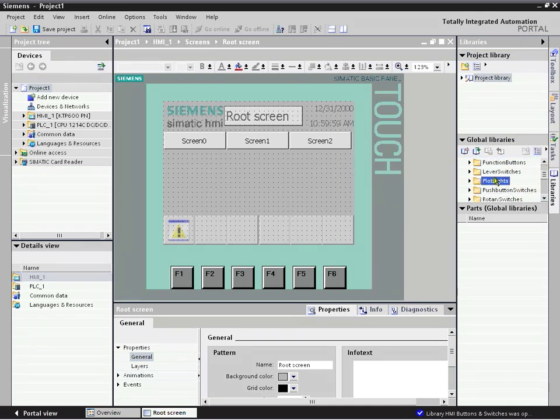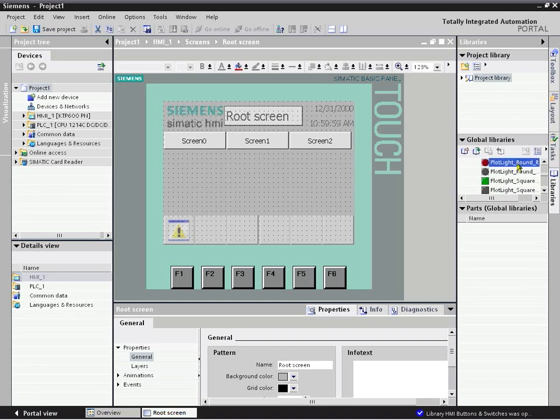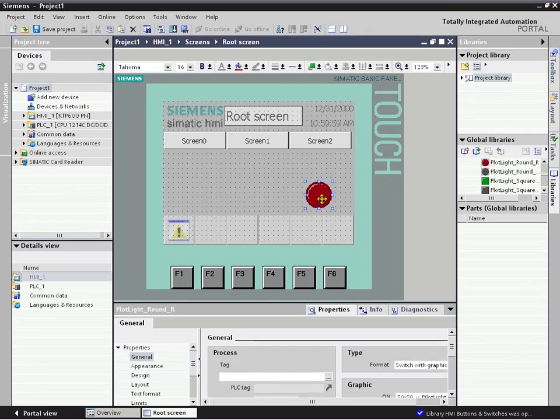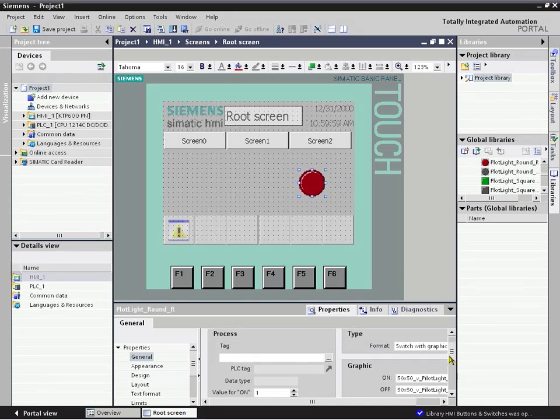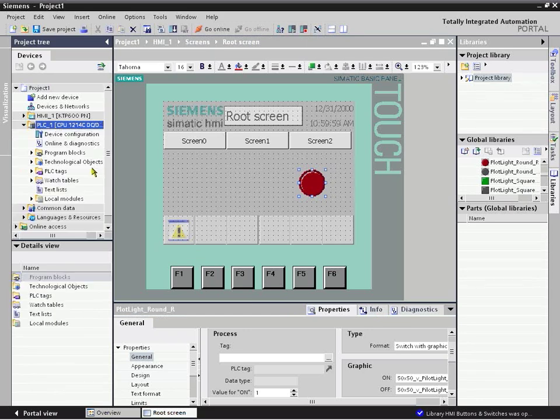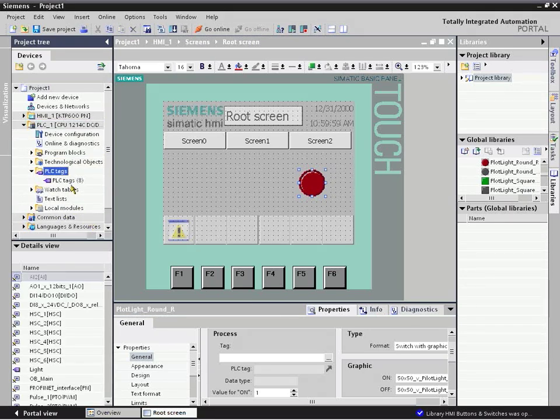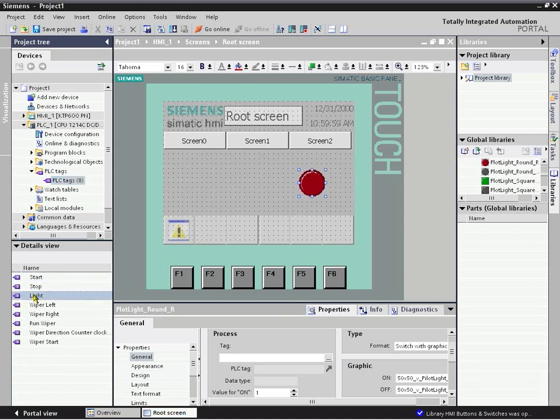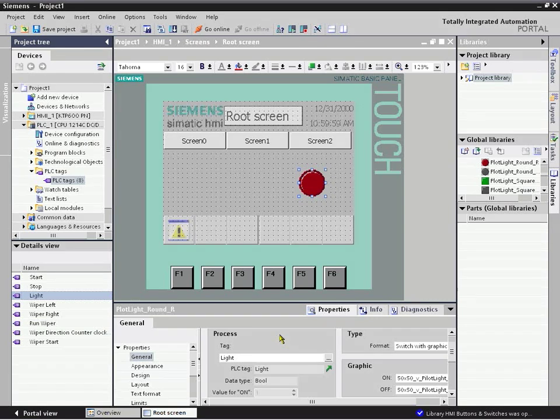We're going to go to the lights, choose a red light to match our hardwired light, and put that on the screen where we want. Since it's a unified program environment for our tag definition, we can go right to the PLC tags because we know we have put a coil for a light, and just simply drag right into our tag field for our HMI. Then it does all the reconciliation and all the connections for you automatically.